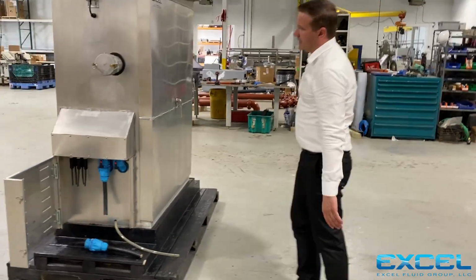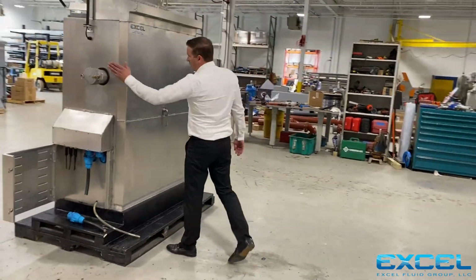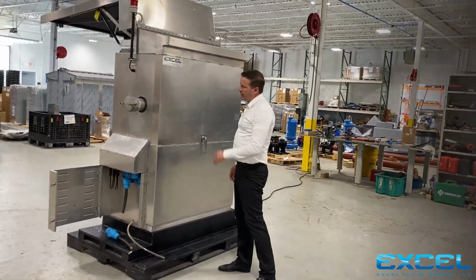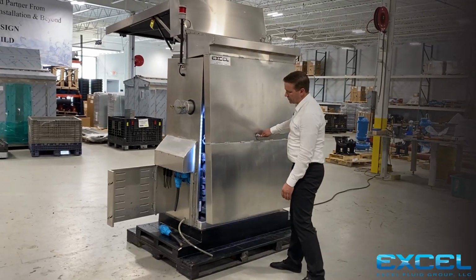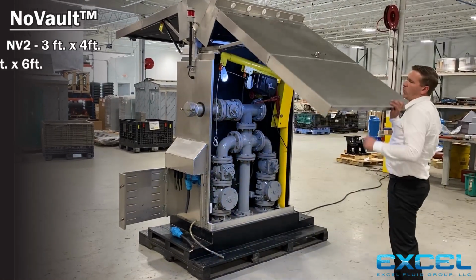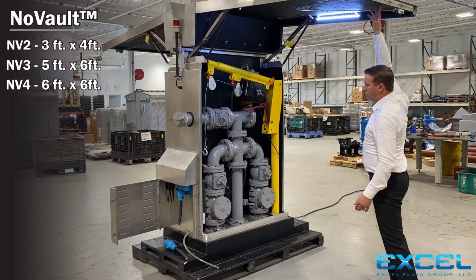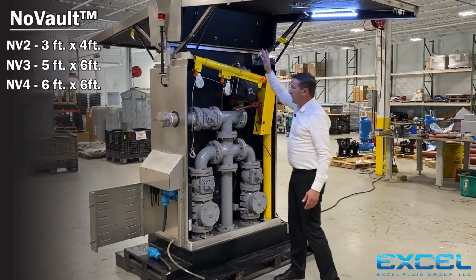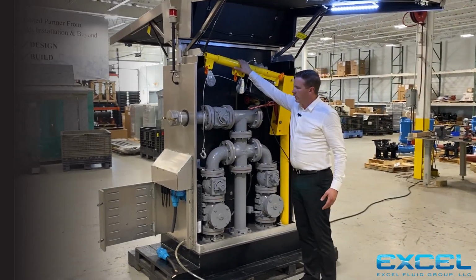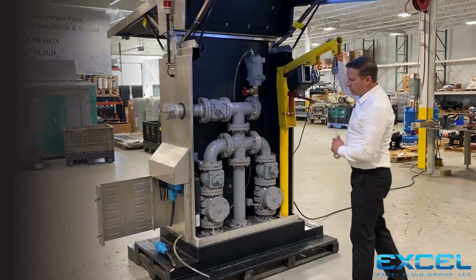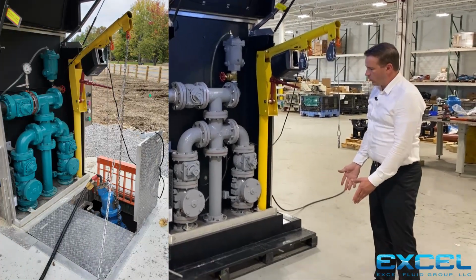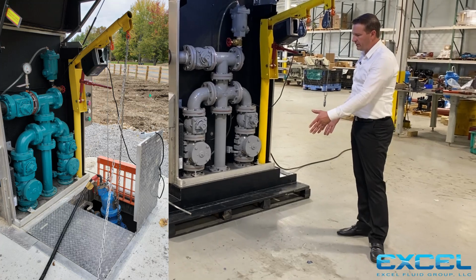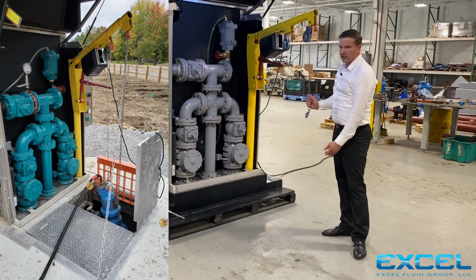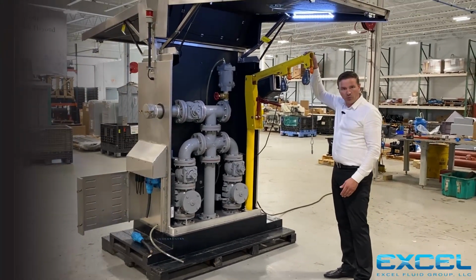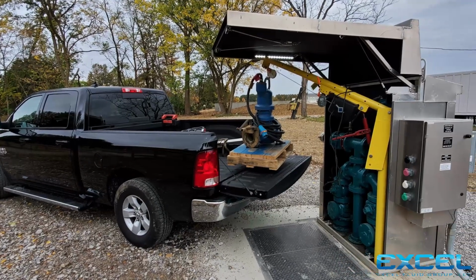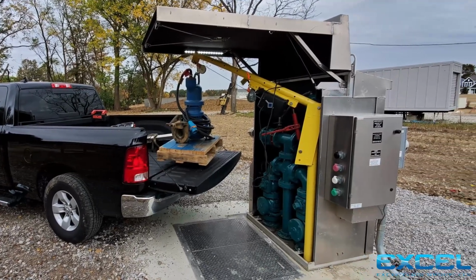Let's take a look at the piping side of the NoVault enclosure. We have our bypass stainless connection point for when that's required for the pump station, and then we can open our gull wing enclosure, again, giving us some shelter, LED lighting, and this one features our optional swing away hoist, which allows us to lift the pumps out of the wet well. We'd be standing on hatch or safety grates, and this electric hoist allows us to lift them out easily. Extendable boom, we can put them right in the back of our pickup, don't even need a service truck.